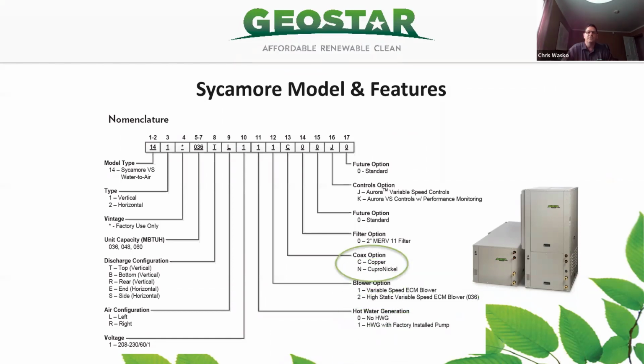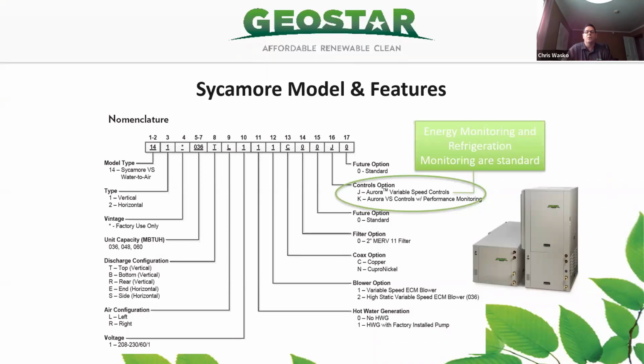The coaxial options for the water, we have a copper and copper nickel, depending on your water quality and the needs and demand for servicing the unit. If you're on an open loop or closed loop, you're able to choose the 2 different options there. The filter is set up as a 2-inch MERV 11 filter. We have control options on it as well, the J and K series on there. So the first one is the Aurora variable speed controls. That also comes with energy monitoring and refrigerant monitoring as standard in that control. So if you move up to the K option, you're getting the performance monitoring added into it.